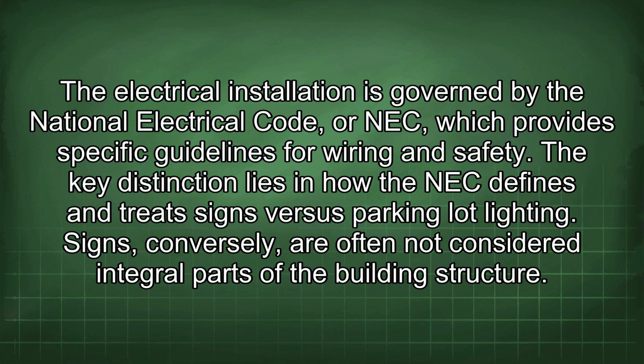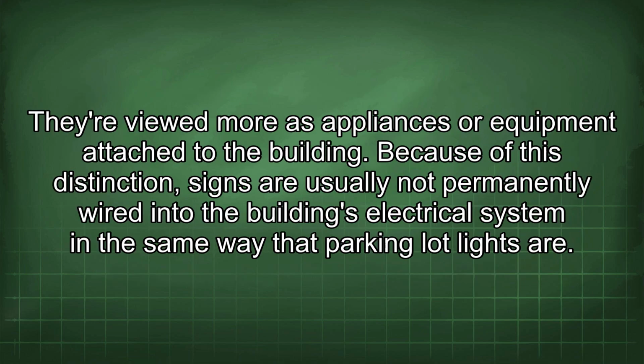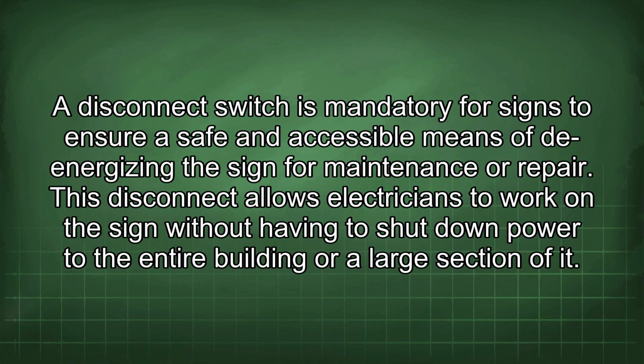Signs, conversely, are often not considered integral parts of the building structure. They are viewed more as appliances or equipment attached to the building. Because of this distinction, signs are usually not permanently wired into the building's electrical system in the same way that parking lot lights are. A disconnect switch is mandatory for signs to ensure a safe and accessible means of de-energizing the sign for maintenance or repair. This disconnect allows electricians to work on the sign without having to shut down power to the entire building or a large section of it.